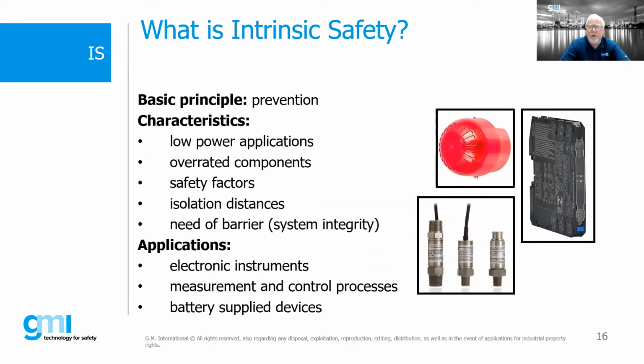So what is intrinsic safety? So again, it's preventing a potential ignition from taking place. So based upon that, it is limited to low power applications. So where we don't see intrinsic safety is where we have high power applications. We don't see intrinsic safety with, say, motor starters or motors. We don't see typically intrinsic safety with lighting products. But when we start talking about our sensors, our devices that are used to actually monitor and potentially control other electrical or other mechanical equipment, that's where intrinsic safety is typically used. So it's low power applications. There are safety factors. There are design characteristics on the components with the infallibility and redundancy that is built into it. There's also some requirements for isolation distances. And of course, there's the requirement for actually using a barrier.